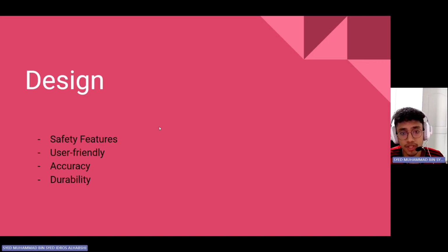For design, the good practices are the safety features implemented, the user-friendly design, the accuracy of the infusion pump, and the durability of the pump. For the safety features, the infusion pump is equipped with sensors and an alarm system, which allows users to take action effective immediately when the alarm is heard. For the user-friendly design, in many of the latest models of the infusion pump, the user interface is actually easier to read and operate, which allows users to use the medical device properly and with ease, minimizing the risk of any incidents occurring, such as overdose.